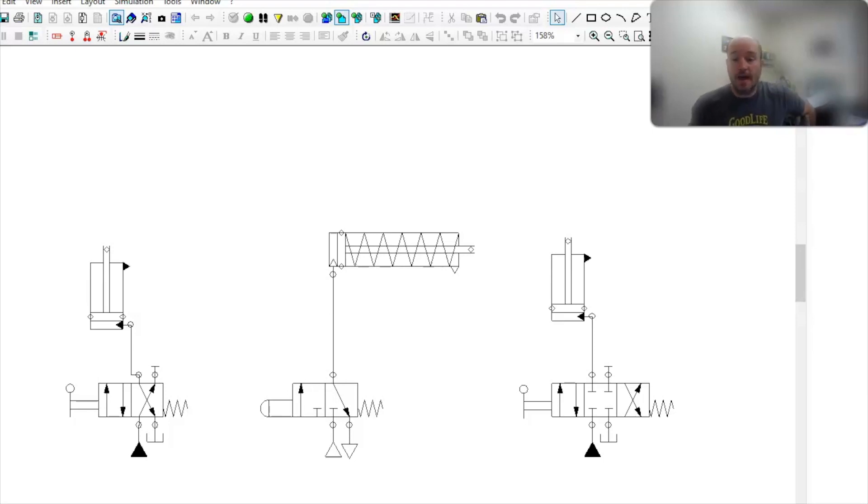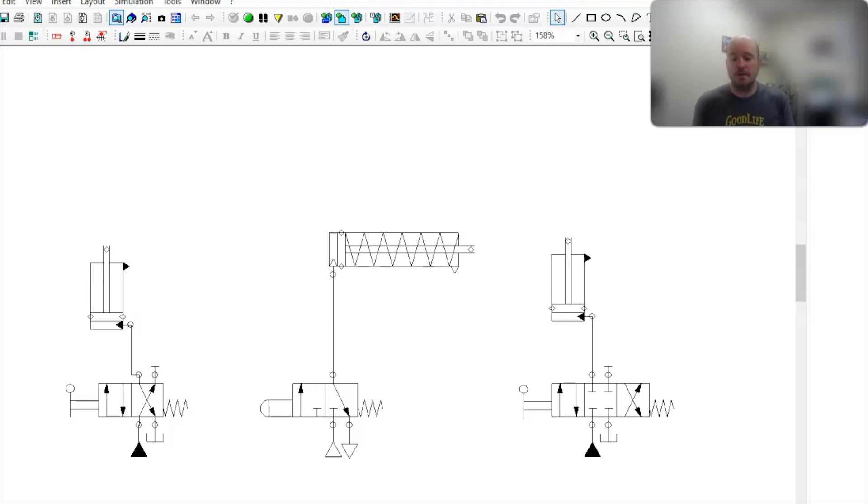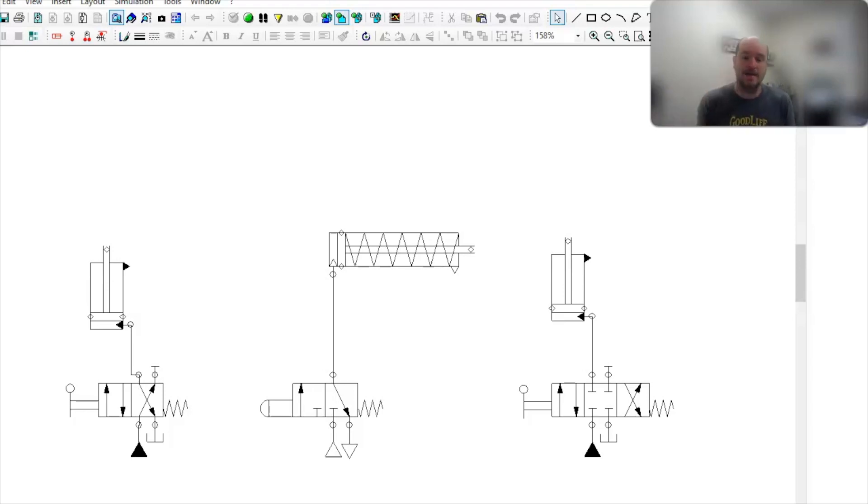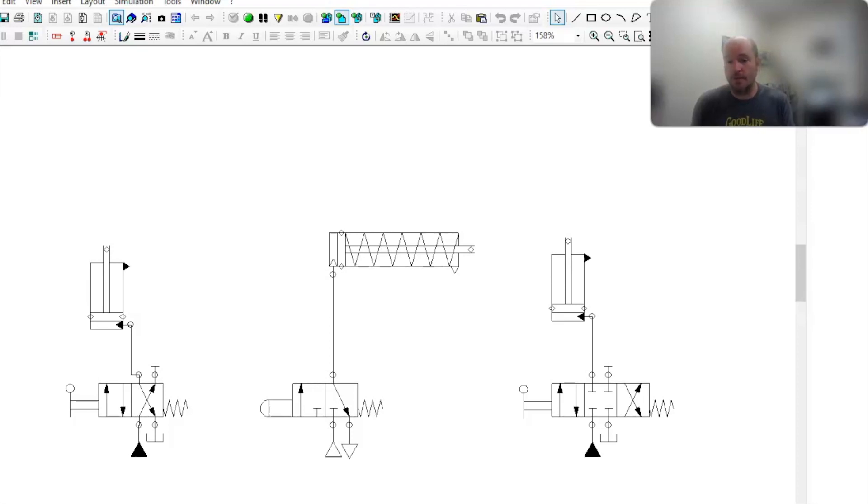And so, now, in rare situations, you may see a 4-3 directional control valve used. This will lock this in place if it's real heavy, although there are some better ways to do it. I haven't seen this done a lot. I think I've seen it a couple times more out of just because that was the only valve they had in stock, and they had to get the machine up and running before. It's not a great look. It's definitely not recommended. But, this would be a 4-3 directional control valve that they have with a closed center, that they have converted by plugging the B port for a single acting cylinder.